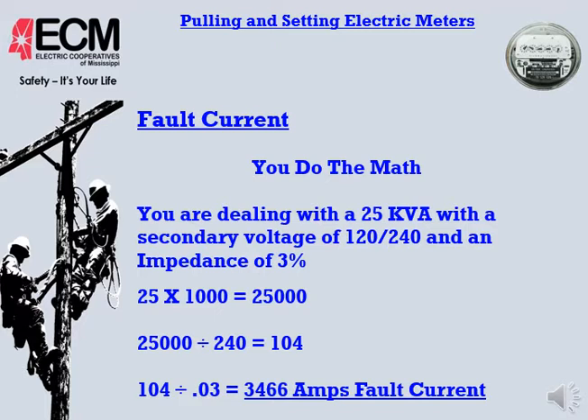if you take this particular problem here, we have a 25 kVA transformer, secondary voltage 120, 240 with impedance of 3%. And if we plug those numbers from the problem above in the equation that we talked about, we take 25, multiply it by 1,000, gives us 25,000. We divide that by 240, which is our secondary phase-to-phase voltage, gives us 104. We divide that by 0.03, which is the 3% of our impedance. 3% of 100, of course. With the percent, we have to change it to decimal form, so it will be 0.03. And that gives us 3,466 amps of fault current available at this location. And now, from this problem, if you look at a 25 kVA transformer, 120, 240, that could be any residential application.